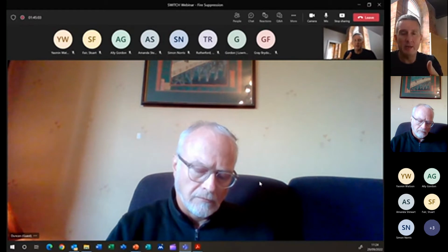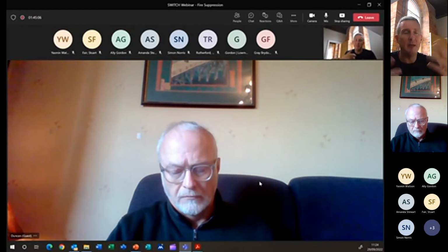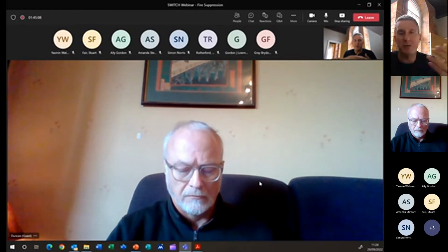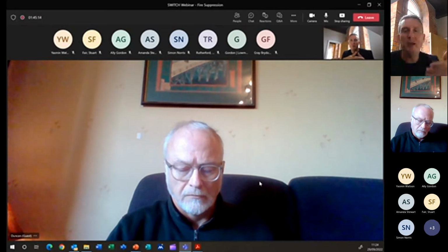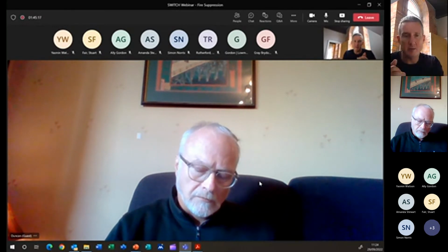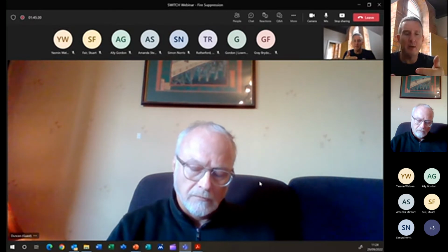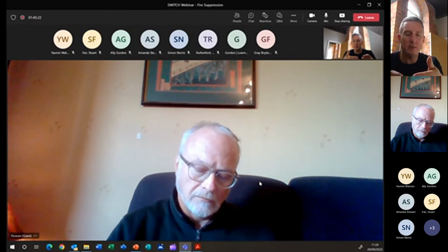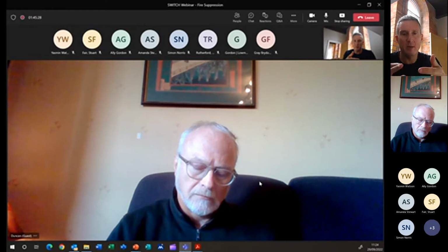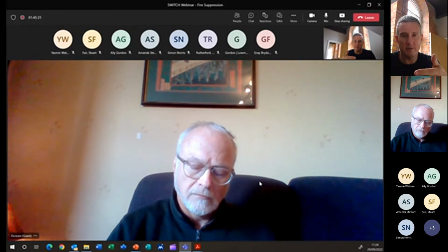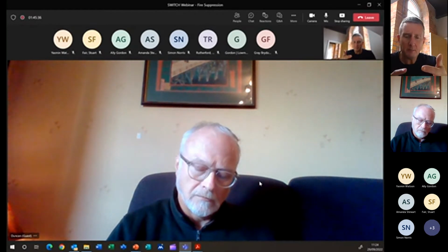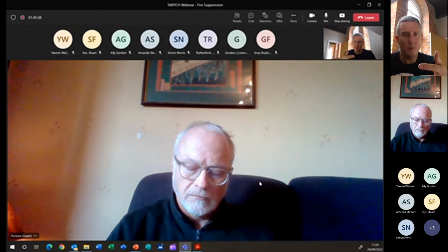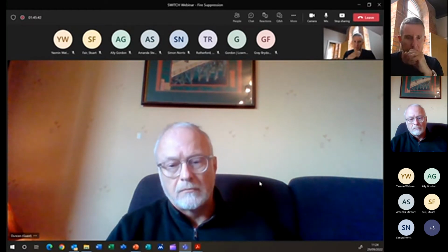Green issues might be a software glitch or something on screen causing a bit of a hindrance but not a massive problem — we have 72 hours to resolve those. Amber means an issue that isn't stopping extinguishing or detection but is causing faults or alarms on the panel — we have 24 hours to resolve that. Red means the system is down from suppression or detection — we have 12 hours to get to site and get it back up and operational.